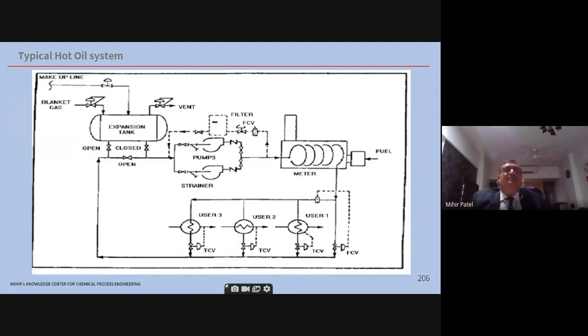So here you can see the circuit basically. There's a hot oil heater on the right, with fuel for burning. The pump on the left of the heater pumps the hot oil through the heater and out to the users. There's a bypass FCV. It goes back through all the users into the expansion tank, which has a blanket gas, nitrogen blanketing, or you can keep fuel gas blanketing also. And then from the expansion tank it goes back to the pumps. It's a circulating system basically. Okay, so this is the hot oil system.